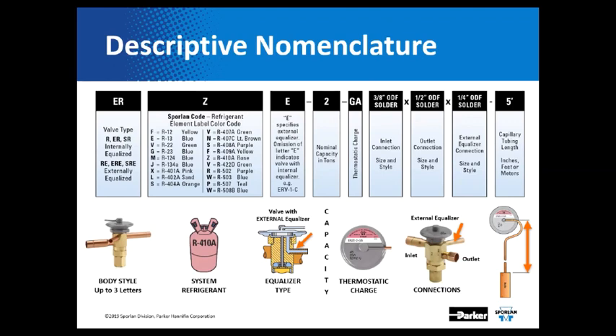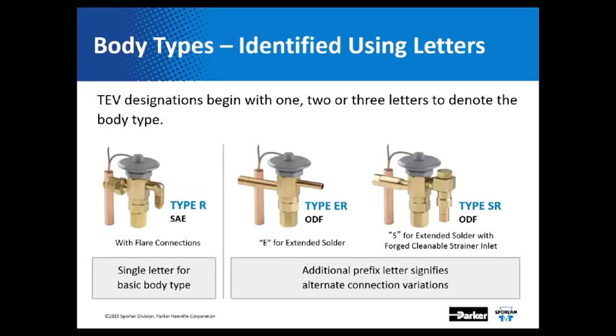After the equalizer there's a dash, and then the nominal capacity in tons. Nominal capacity is what the valve is tested for under specific conditions — it's not always going to be the case in practice. Following the nominal capacity is another dash, and then the thermostatic charge. The thermostatic charge is the power head, and it relates to the refrigerant as well as the application and the evaporator temperature you're working with. After that are all of the connection sizes: inlet connection, outlet connection, external equalizer connection size if present, and then a dash and the capillary tube length.